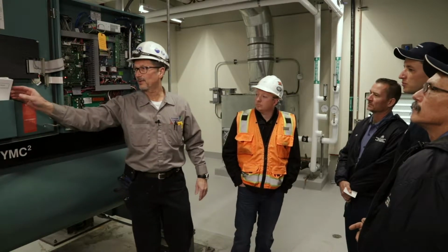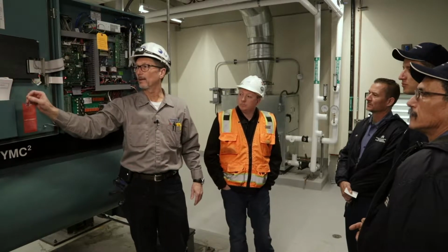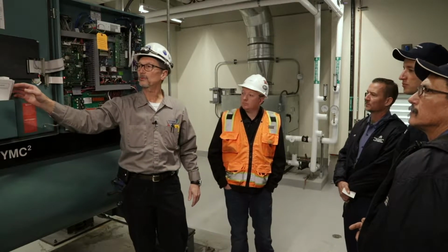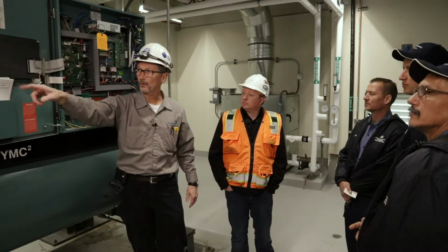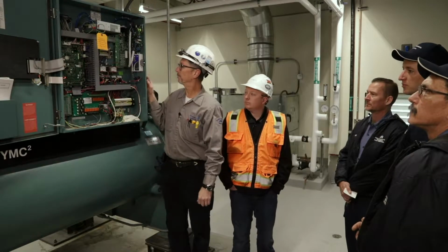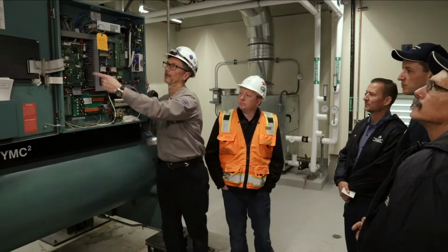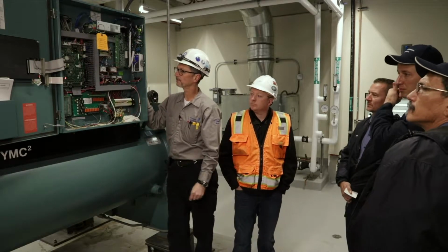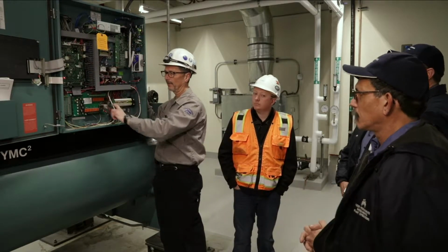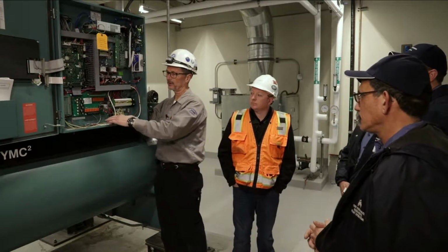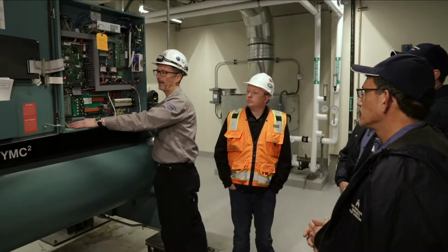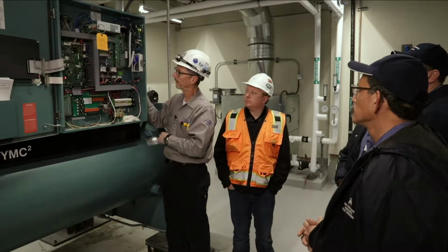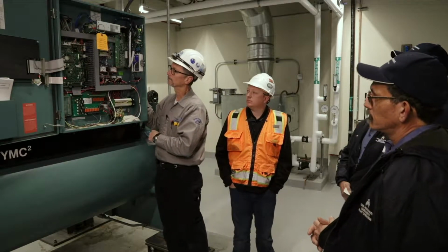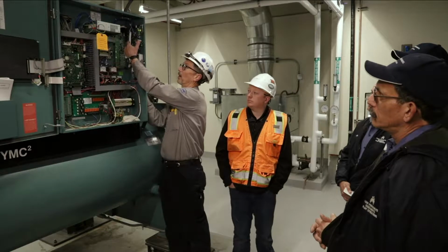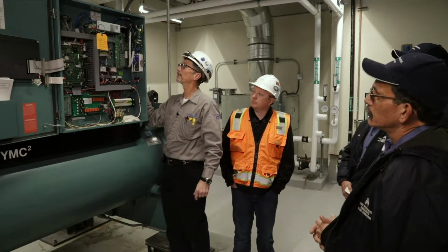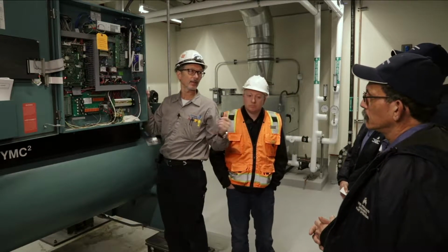So first of all, here's the guide that I was talking about. And then there's some other literature that talks about the motor and the frequency drive as well. And here's the main control board, the brains of the chiller. This is an I/O board that controls inputs, analog and digital inputs, and then the COM card is up here that communicates with the energy management system.